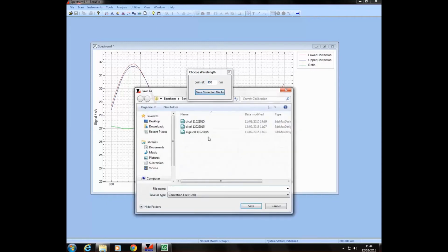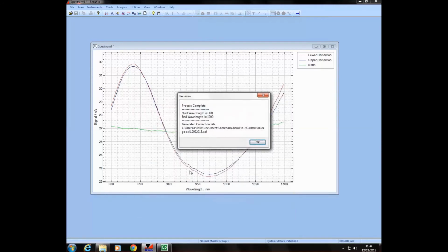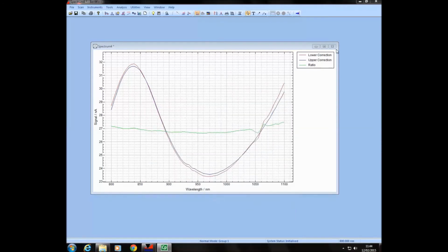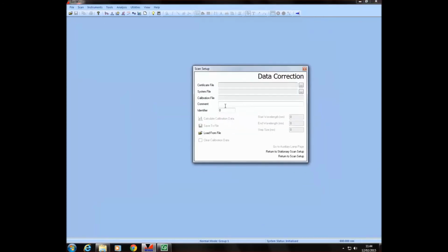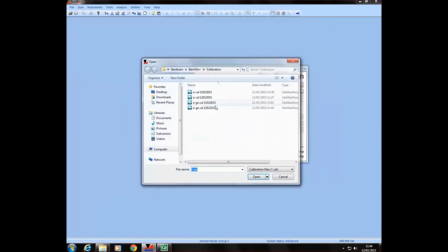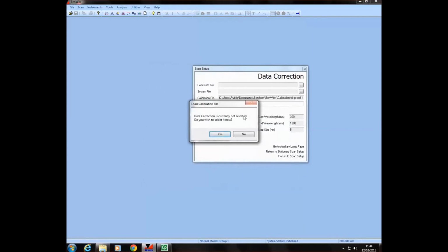We shall save to correction file, maybe calling it SI GE cal, and today's date. I say OK, and we can close this window, no need to save. Two last steps. In scan data correction, we should load from file the silicon germanium calibration we have just generated. Data correction is not selected. Do you wish to select it now?